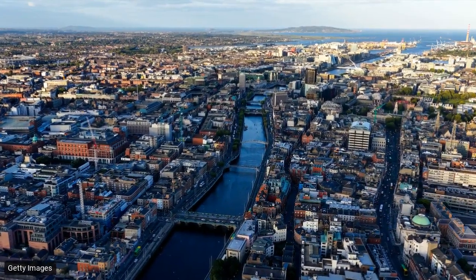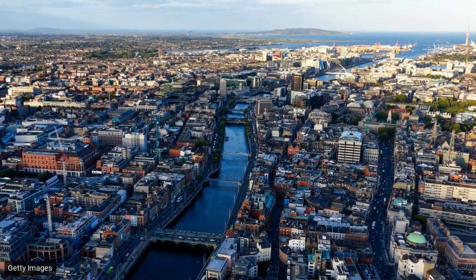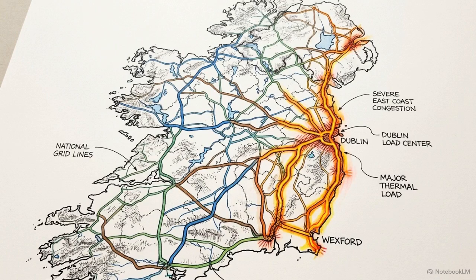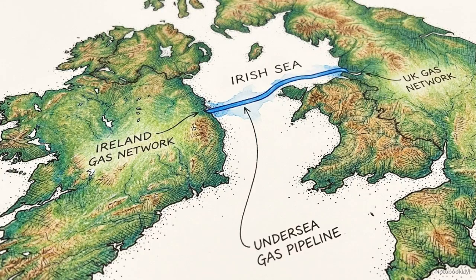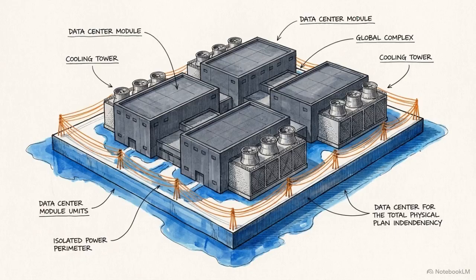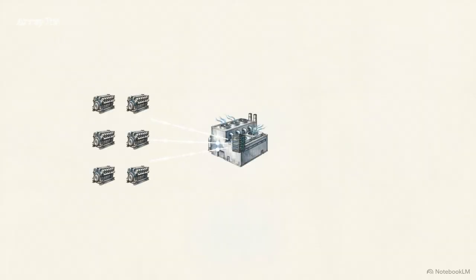The Irish grid faces severe constraints. With new connections blocked and a reliance on a single gas pipeline from the UK, the facility requires high levels of self-sufficiency. The solution involves an array of 6 Everllence 18-cylinder 5160 dual-fuel engines. These engines deliver a combined output of 111 megawatts. The dual-fuel system ensures the data center can operate at full capacity even if the national gas pipeline is disrupted. In peak plant mode, the facility exports power back to the public grid during periods of high demand or low renewable generation, supporting national grid stability.